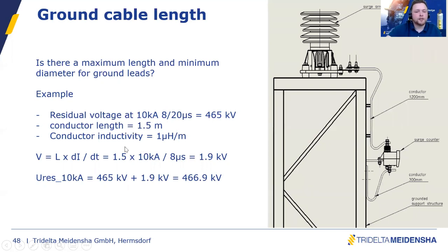As a rule of thumb, we assume that the conductor inductance is around 1 microhenry per meter. There's a very standard formula of electrical engineering: the voltage drop across a conductor with a certain inductance, at a change of current over a certain change time, is 1.5 meters times 1 microhenry per meter times 10 kA divided by 8 microseconds. I forgot the inductance here on the slide. So the result is that the voltage drop along this cable will be 1.9 kV in this condition.